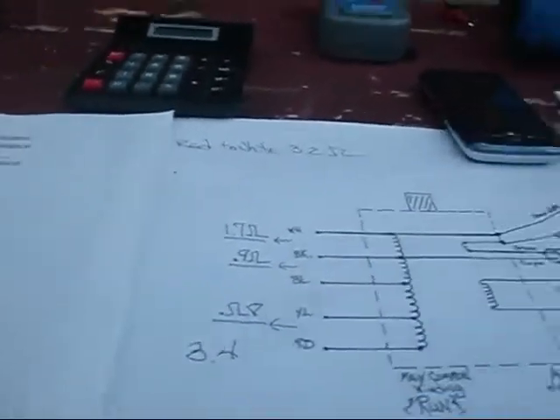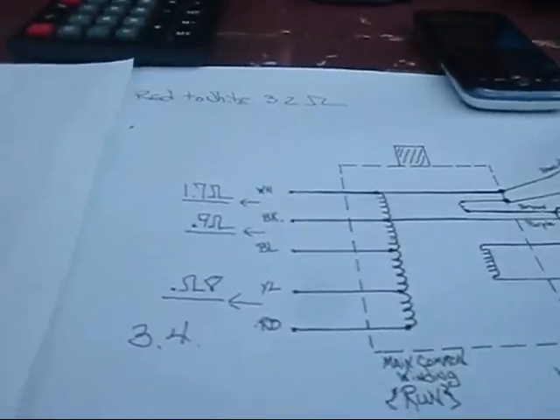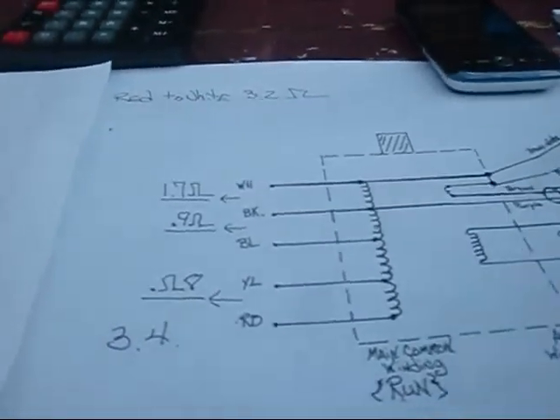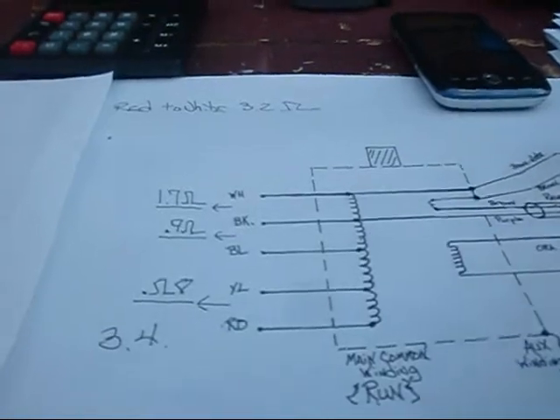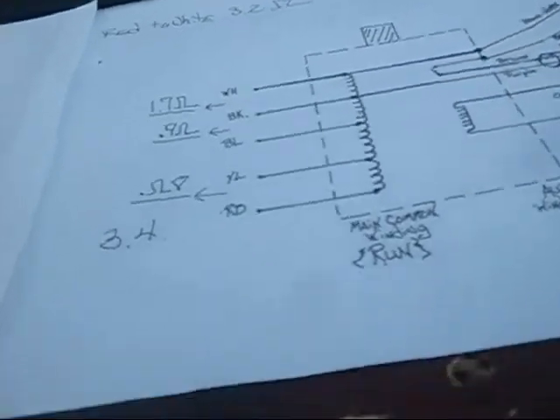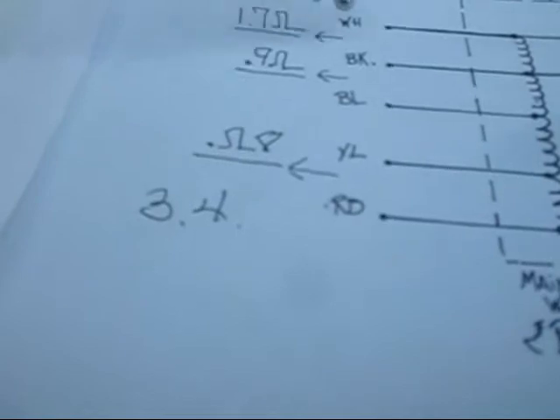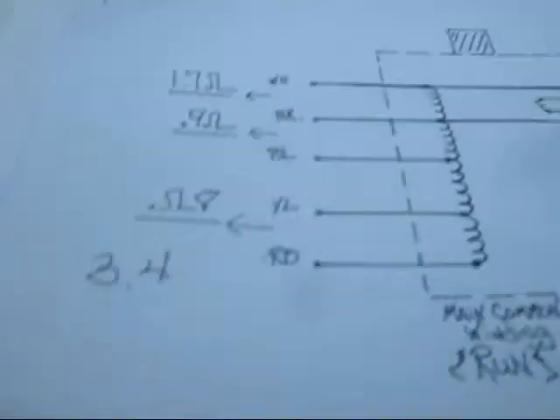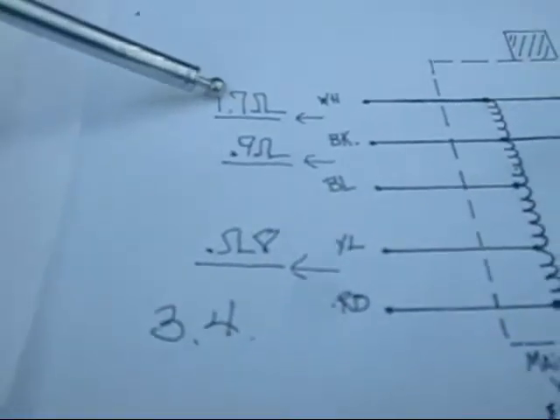After we conducted that test, we came over here and got on this nice little drawing that an engineer from Florida was kind enough to send me. What we did here was we took our white to our black and we got 1.7. Then we took our black to our blue, we got 0.9. Then we took our blue to our red, we came up with 0.8. We added these up, and we came up with 3.4. Then we tested from red to white and we came up with 3.2. So we're definitely in the ballpark here.